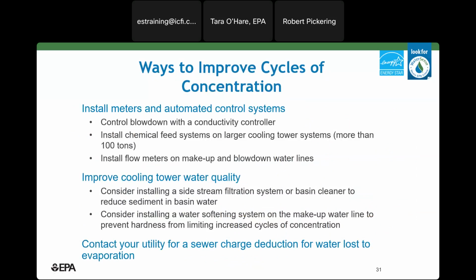In terms of retrofits that you can do to get the most efficiency out of your tower, first is to install an automatic controller that controls blowdown based on conductivity to maximize your cycles. You can also install makeup and blowdown meters to track your water use on an ongoing basis and monitor trends, taking corrective action if necessary.